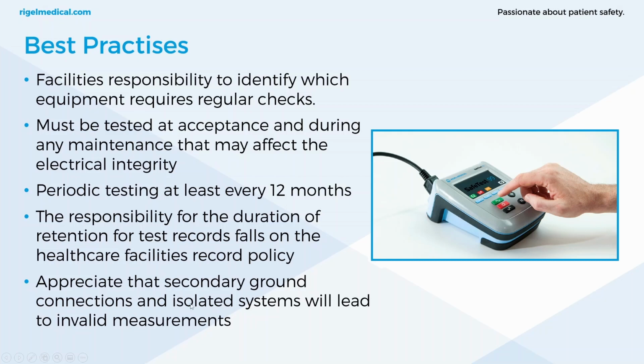Also appreciate that secondary ground connections and isolated systems will lead to invalid measurements. Now our safety analyzers do have these prompts, so if that does show up, then you know you need to either disconnect that device from the secondary earth, or you need to move the safety analyzer and the device to a TN system.